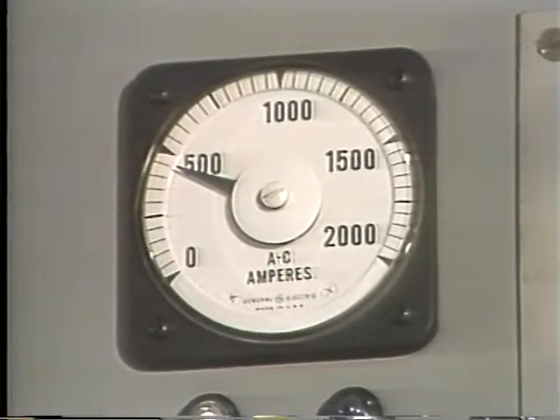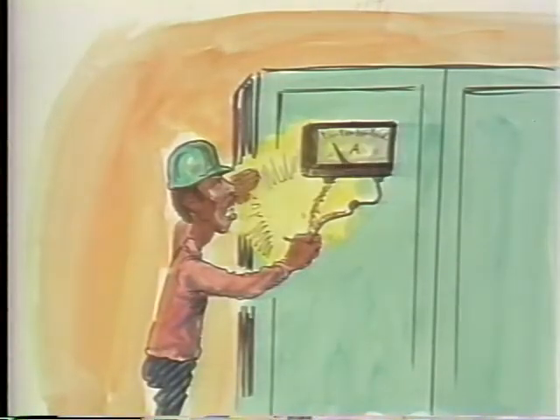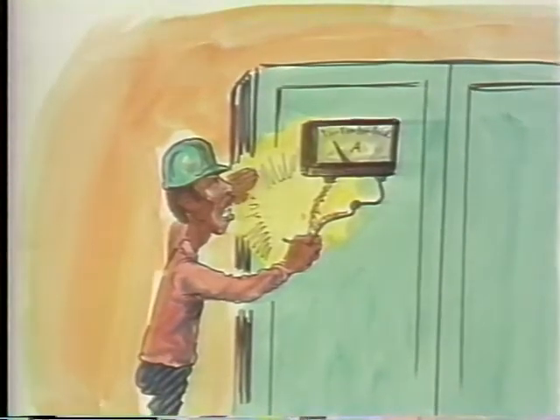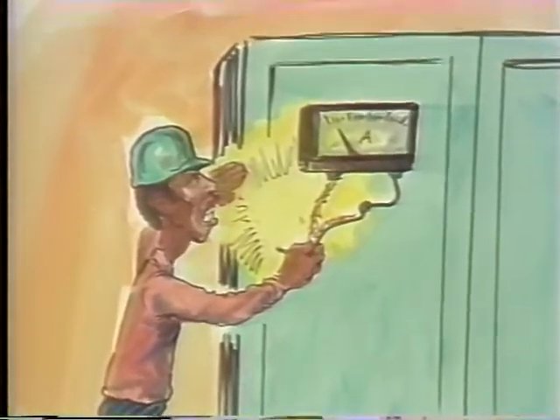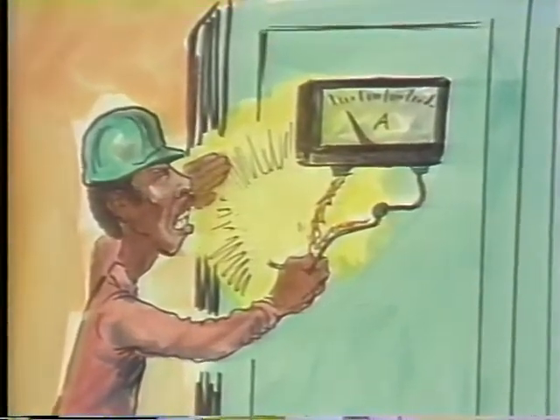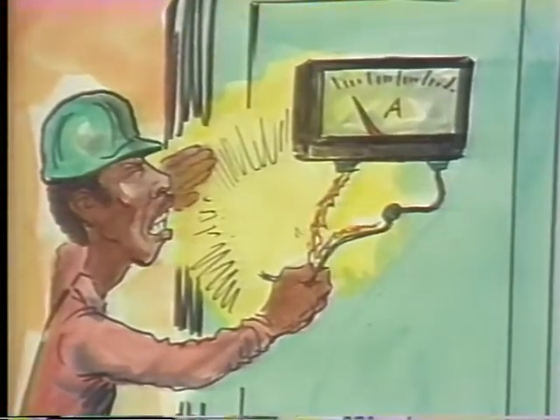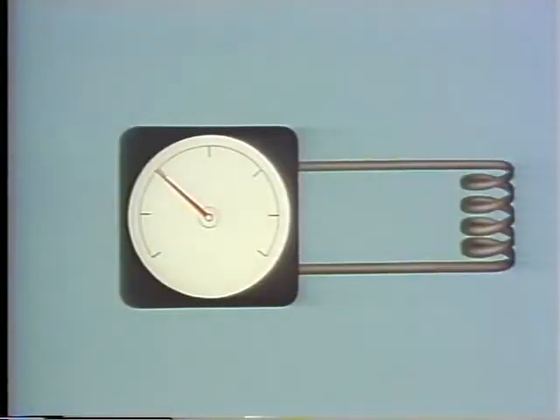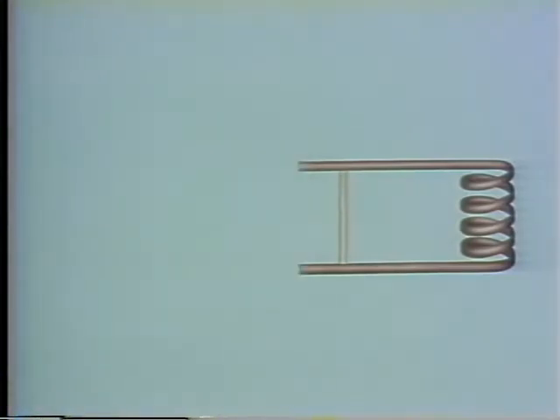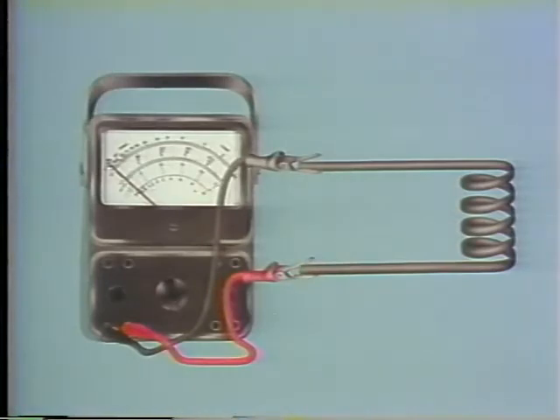For example, say you had to test an ammeter. Would you just unhook the meter and plug in a portable? If you did, you'd have a surprise coming to you. When you break the secondary of a current transformer, voltage zooms up, enough voltage to weld with. To be safe, you have to short the secondary instead. Then it's okay to disconnect the panel meter and plug in a portable. It's better to de-energize everything first, but if you can't, remember, never open the secondary of a current transformer.